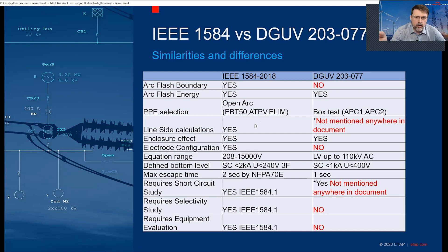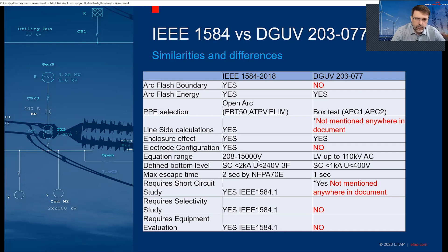Do we calculate line side? In IEEE 1584 it's very clearly stated we should. In DGUV it's not mentioned but technically possible. Enclosure effect: yes, both have it. We don't have electrode configurations in DGUV. Equation range: IEEE covers 208V to 15kV; DGUV states low voltage up to 110kV — though that upper range is something to discuss, since there are no background calculations given to prove it.